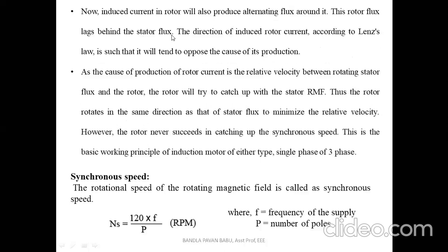Definitely it has to lag, otherwise there may be a chance of magnetic locking. So there exists the concept of slip. And one more thing, there is a gap between the stator and the rotor, which may be from 0.4 mm to 4 mm as per the requirement of the HP, based upon their horsepower levels. So this gap may vary. But definitely there should be a lagging between the rotor flux and stator flux.